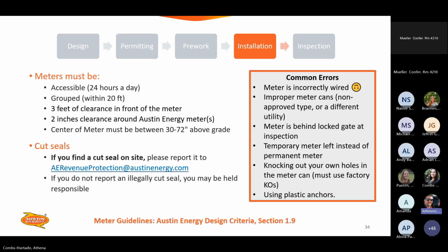All right, meters must be accessible 24 hours a day. They also must be grouped within 20 feet of the revenue meter. There does have to be 3 feet of clearance in front of the meter for the voltages that we work with typically day-to-day, 2 inches around the meter, and the center of the meter must not be below 30 inches or higher than 72 inches above your finished grade or platform to the center of the meter can.